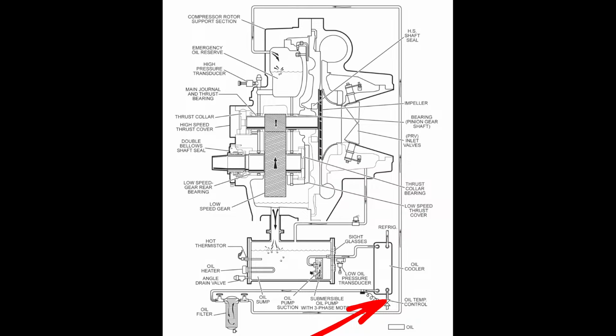So your refrigerant charge level or refrigerant level control period does have an impact on this. So are we feeding a consistent and subcooled refrigerant to this metering valve? If we're not, that may be affecting, especially at high loads, how much refrigerant we're actually feeding to the oil cooler. So if we're not feeding enough refrigerant to the oil cooler, that could be why we're seeing these temperatures increase, which at that point, what you're going to see is the temperature as it returns back into the sump increasing. So when we say the temperature is increasing, we're seeing the sump temperature increase specifically, which means that it's already made its way all the way back around. And this should be basically, well, I guess not our coolest point, but it's our return point coming back out of the compressor. So just bear that in mind with this particular system.